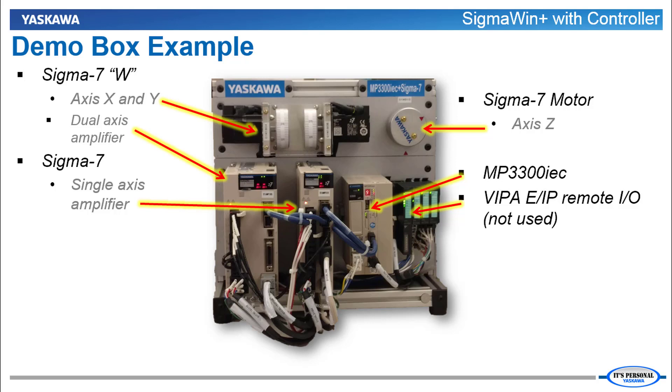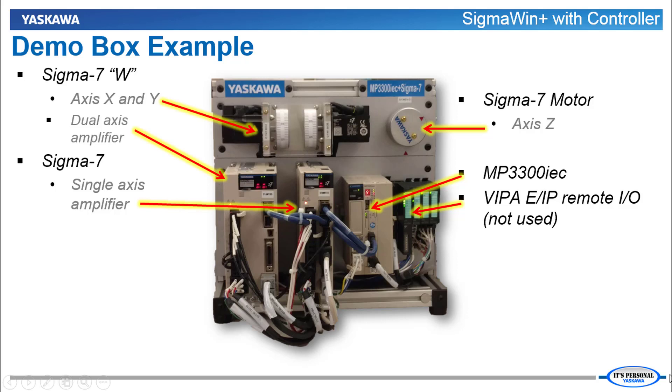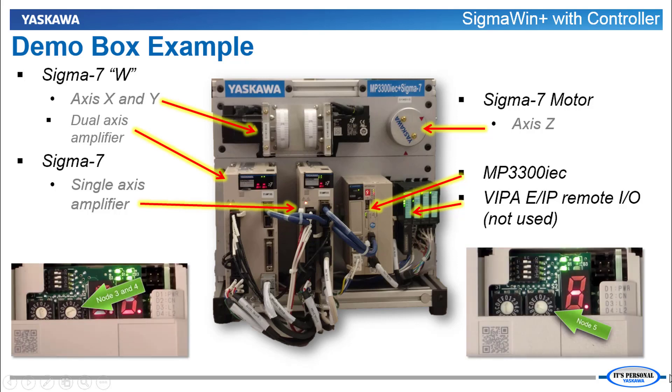For this demonstration I'm using the standard MP3300 IEC and Sigma 7 demo. We've got the dual-axis amplifier running two motors on the top. The single-axis amplifier runs the motor on the right. Both servos are connected by Mechatrolink 3 to the MP3300 IEC controller. The dual-axis amplifier is set for network nodes 3 and 4 while the single-axis amplifier is set as node 5.